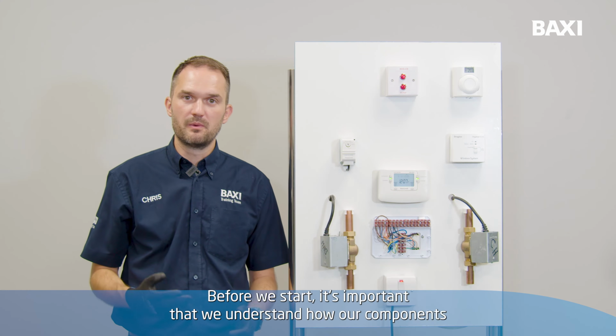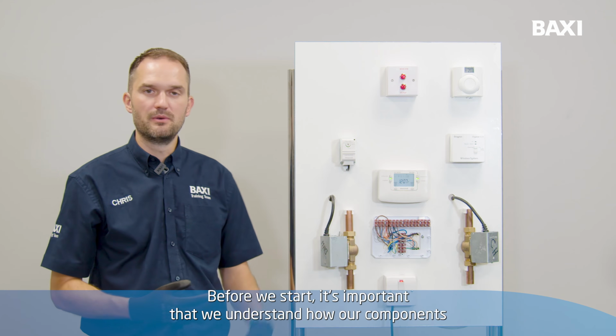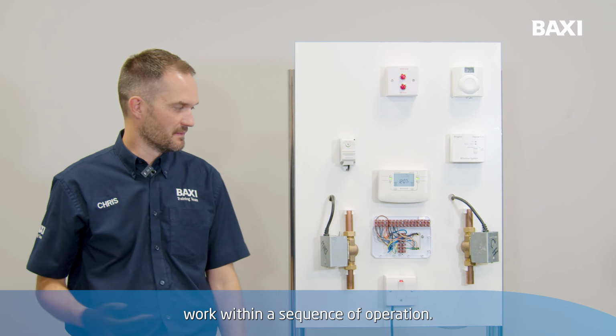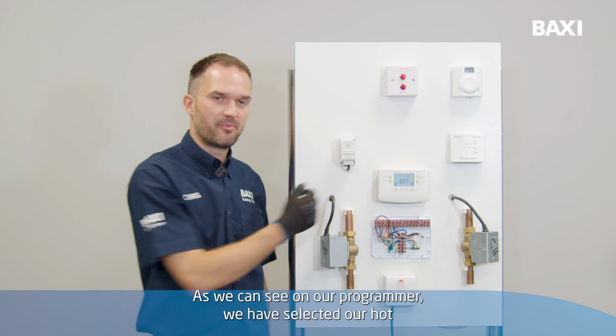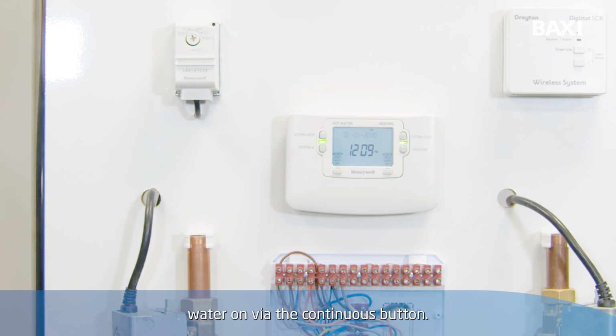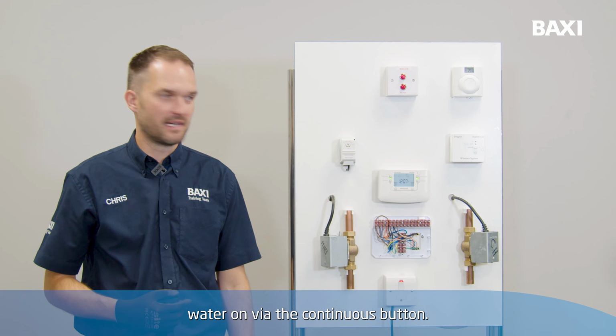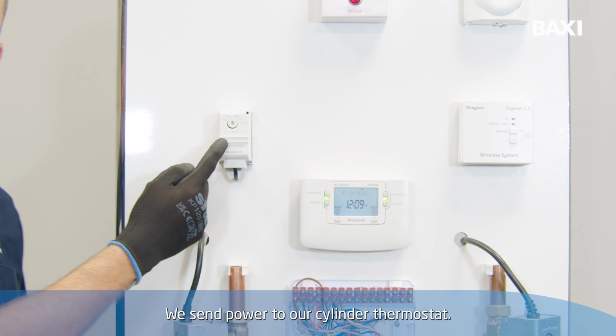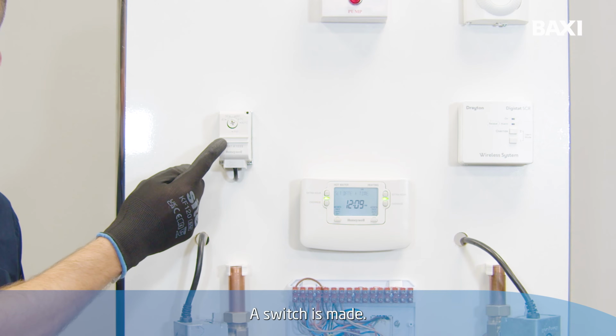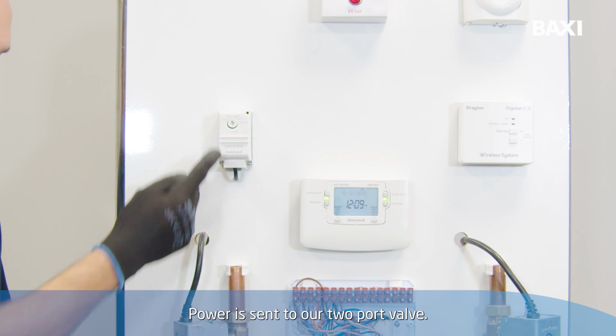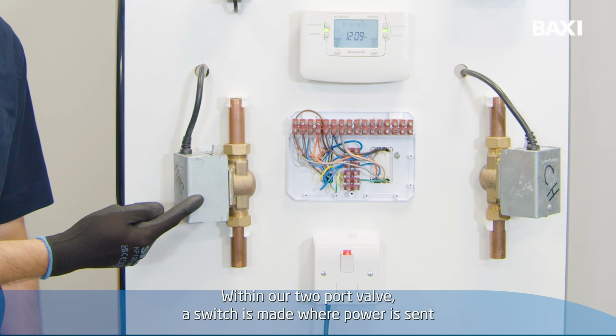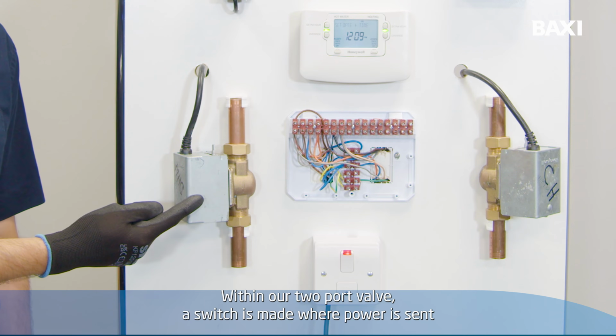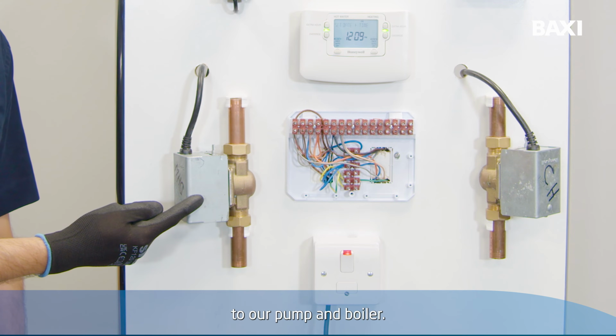Before we start, it's important that we understand how our components work within a sequence of operation. As we can see on our programmer, we have selected our hot water on via the continuous button. We send power to our cylinder thermostat. A switch is made. Power is sent to our 2-port valve. Within our 2-port valve, a switch is made, where power is sent to our pump and boiler.